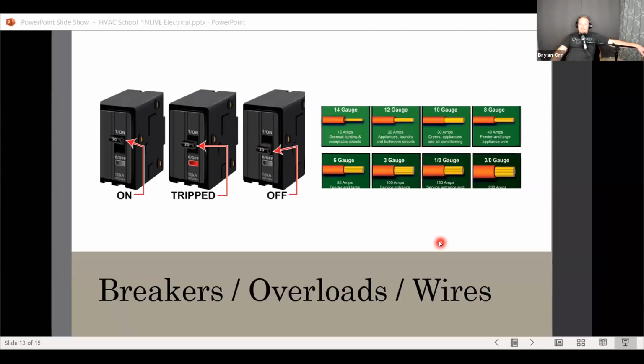Because wire sizing is not as simple as this chart right here. So this chart shows 14 gauge is 15 amps, 12 gauge is 20 amps, 10 gauge is 30 amps. These are all based on sort of worst case scenario applications using, I think it's, 60 degrees Celsius wire, which is what NM is. NM means non-metallic. That's what we call Romex, trade name Romex, right? And so when we're used to working in residences and they have that 60 degrees Celsius insulation on them, or it's Romex, this is where these sizes come from. But also this is copper.